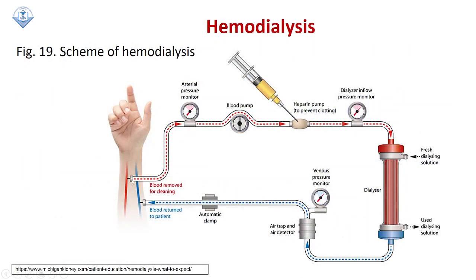This diagram shows what happens: blood is removed from the patient's arm through a specific access point and moved to a compartment with dialyzing solution. Blood is pumped and heparin is added to prevent clotting. Inflow pressure is monitored, the dialyzer processes the blood, and then the cleaned blood is returned to the patient's bloodstream via a venous pressure monitor with an automatic clamp.